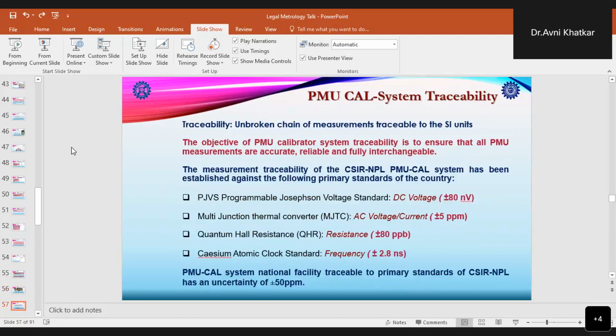And as we are talking about the traceability of this PMU calibration system, as we all know, traceability is an unbroken chain of measurements which are traceable to the SI units. So the main objective of having traceability of the PMU calibrator system is to ensure that all the PMU measurements are accurate, reliable, and fully interchangeable. The measurement traceability of the CSIR NPL PMU calibration system is established against the primary standards of the country. For the DC voltage, we have PJVS, that is the programmable Josephson voltage standard. For AC voltage and current, we have multi-junction thermal converters, that is MJTCs. For resistance, the quantum Hall resistance standard is used, and for frequency, the cesium atomic clock standard is used. So the PMU calibration system is traceable to the primary standards of CSIR NPL.